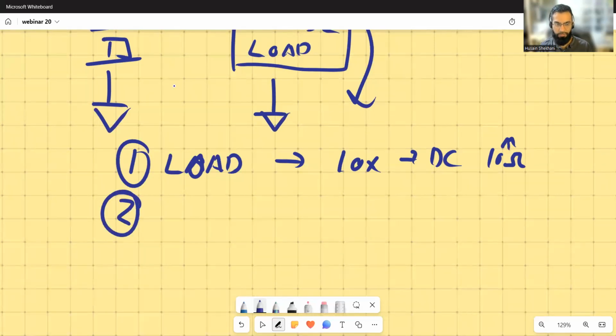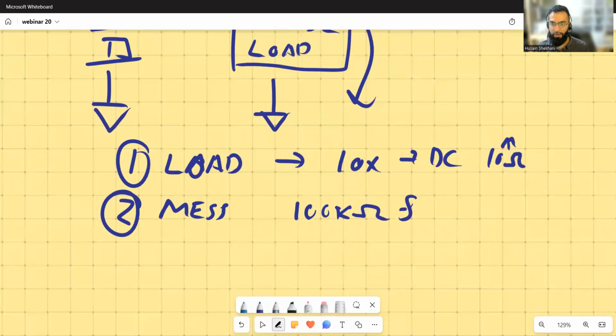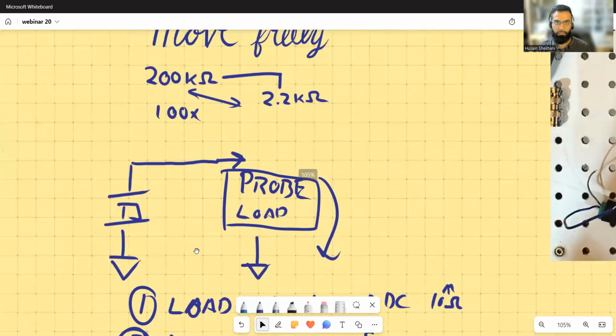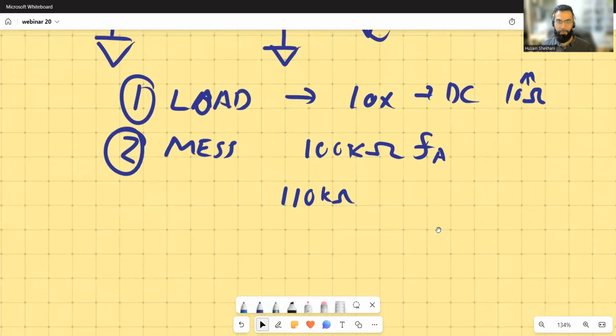So hey, that's not going to disturb the circuit. That's one thing. You don't want to load some circuits, and also you could mess up the measurement by the input impedance of the probe itself. So if you're trying to measure a 100 kilo ohm anti-resonance, and I'm giving you a 110 kilo ohm input probe like this, that's a bad idea. You're not going to be able to measure that properly. It's going to drop voltages, because the circuit you're trying to measure is now part of the measurement circuit. So the higher the input impedance of your probe, the better.